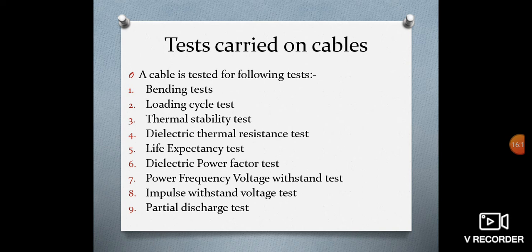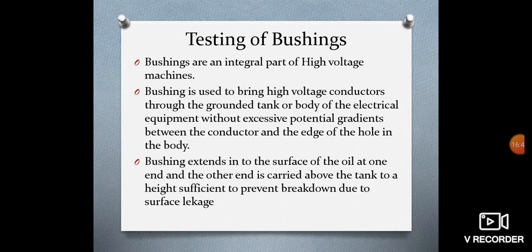As a result, there is a sudden dip in voltage in the form of an impulse. This impulse travels along the cable, and the duration between the normal pulse and the discharge pulse is measured on the oscilloscope. This gives the location of the void from the test end of the cable. However, the shape of the pulse gives the nature and the intensity of the discharge. So these are some of the tests carried out on cables.